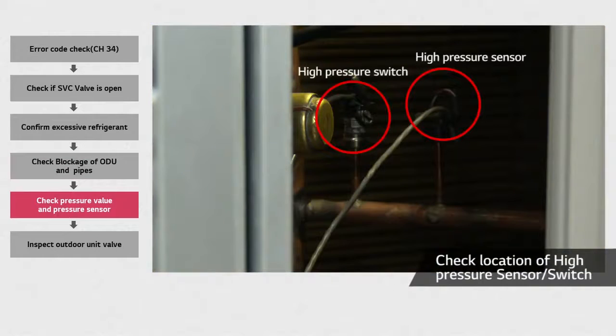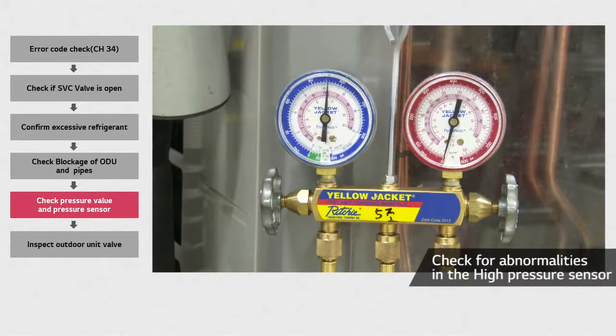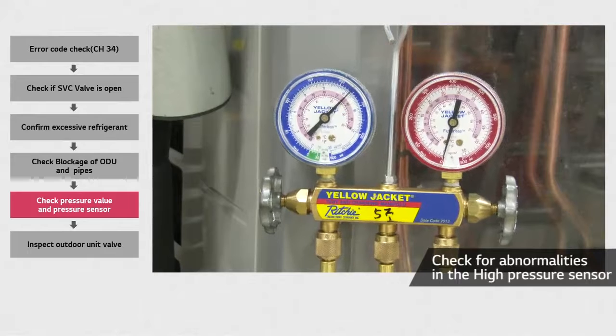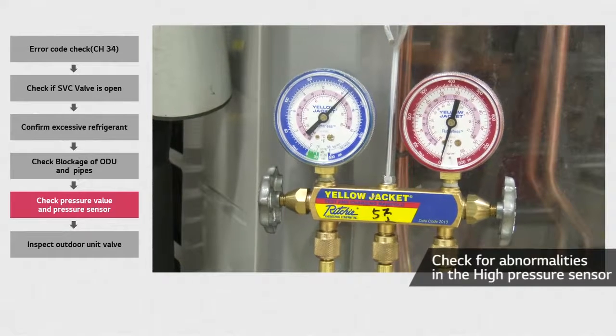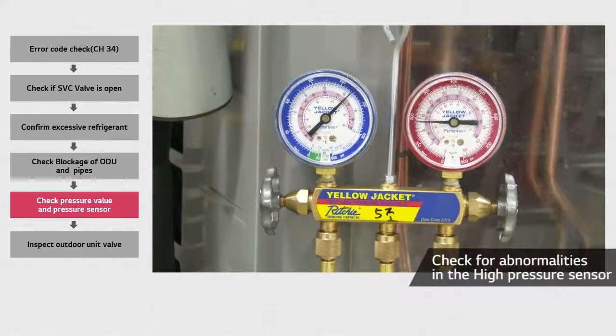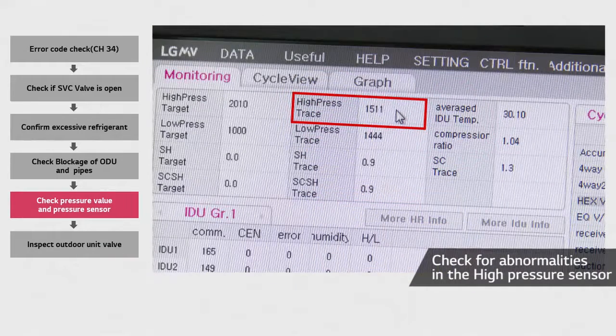Locate the high pressure sensor and the high pressure switch. The high pressure sensor is on the right, and the high pressure switch is on the left. When measuring the refrigerant pressure, use a manifold gauge. As a needle rises, you can check the increase in pressure. Connect the blue line with the low pressure valve and the red one with the high pressure valve. Then, compare the refrigerant pressure values from the LGMV and the one from the manifold gauge. If the values differ a lot from each other, you can assume the sensor to be damaged.